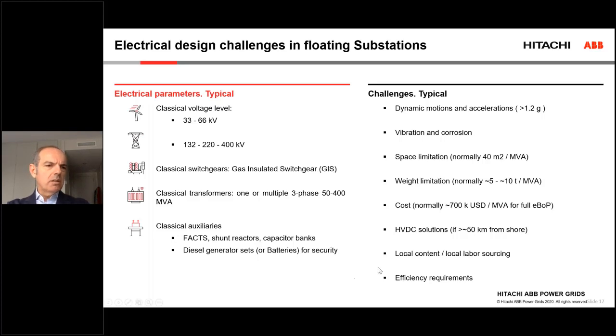Just a few words about the electrical parameters. Classical voltage level from wind turbines to floating substations is 33 to 66 kilovolts. Mainly in offshore application, we are talking about 66. However, due to the increasing sizing of the power in the wind turbines, probably in the coming future, the 66 will be becoming 132, particularly due to the additional length of the cables and increase of distance between one wind turbine and the other due to the power itself.